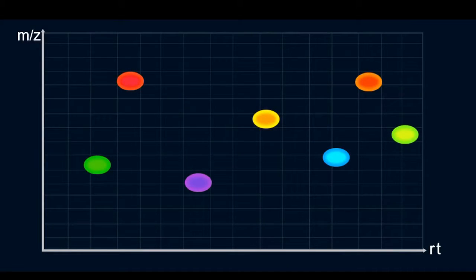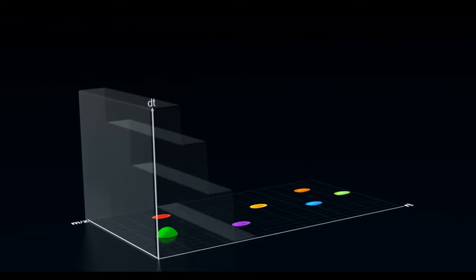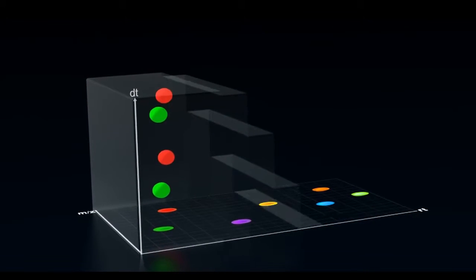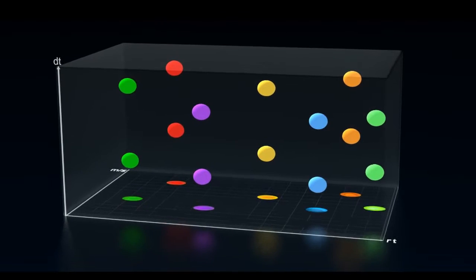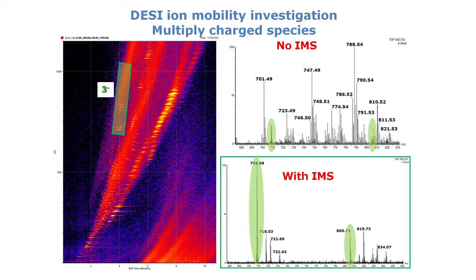That's what people mean when they say it's nested. This gives us added peak capacity or separative capability, which can be really useful if you've got complex samples. It allows you to separate species better and delve deeper into the samples for things that would otherwise have been hidden by other species. It's also useful for direct sample introduction techniques such as MALDI or DESI, where you don't have any chromatography up front — you can use the mobility separation in the instrument to give some degree of separation for those samples.